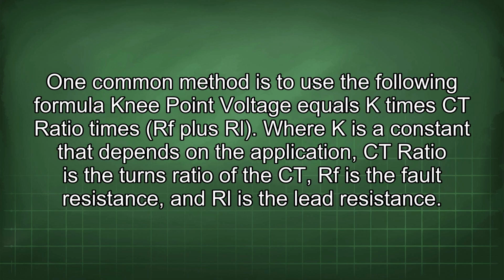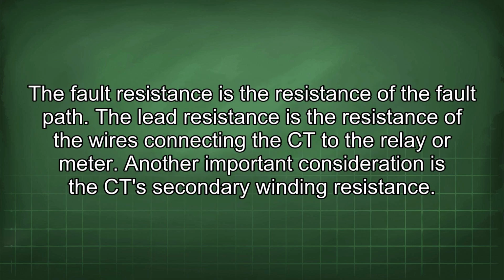There are several methods for calculating the required knee point voltage. One common method is to use the following formula: knee point voltage equals K times CT ratio times (RF plus RL), where K is a constant that depends on the application. CT ratio is the turns ratio of the CT, RF is the fault resistance, and RL is the lead resistance. The fault resistance is the resistance of the fault path. The lead resistance is the resistance of the wires connecting the CT to the relay or meter.